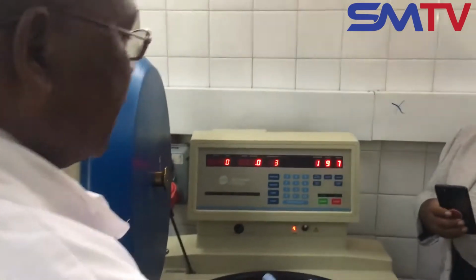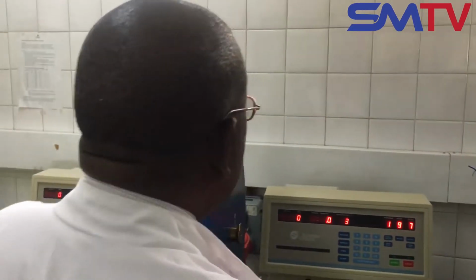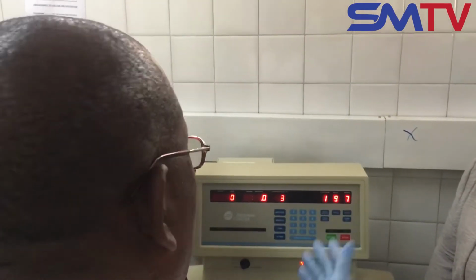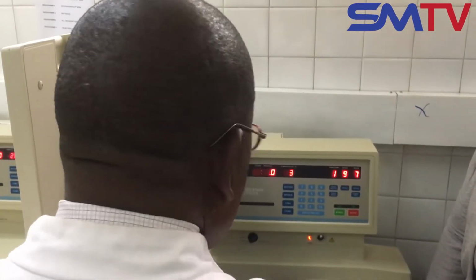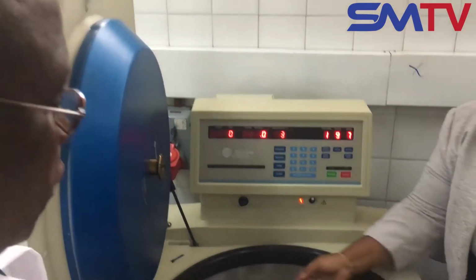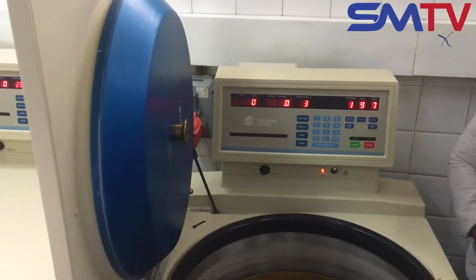Depending on the product we are doing, like I said, the packed cell, the FFP, we spin them at, I talked about the temperature, at 4 degrees. As you can see, the temperature here is 3 degrees. At 4, plus or minus 1 degrees. And you can feel the chamber here, it's cold.